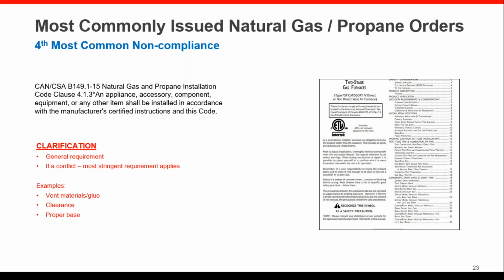And again, we see issues around improper venting materials, or the wrong glue used to put vents together. With the advent of the plastic vents over these years, we've seen a lot of issues with mismatching materials and glues and that kind of thing, or no glue at all. And also, like I said, clearances and ensuring that the appliance has a proper base. I don't have a picture today, but I have one that I use where a water heater is sitting up on blocks, and it's just not acceptable to be a proper base for a fuel-fired appliance.